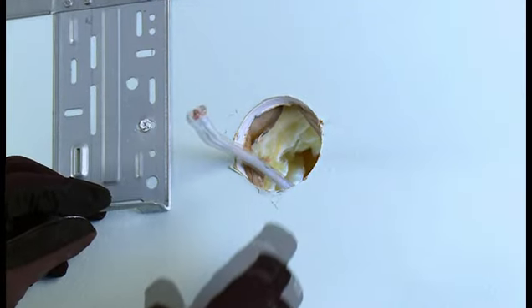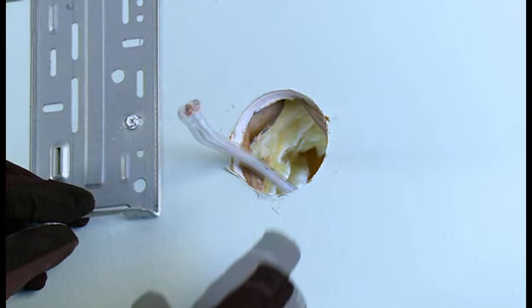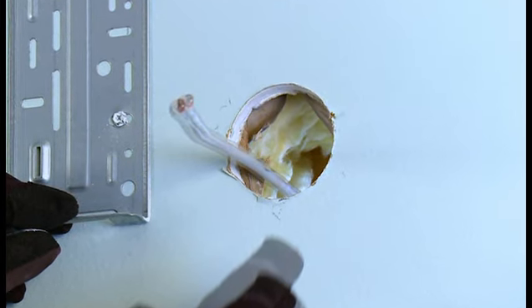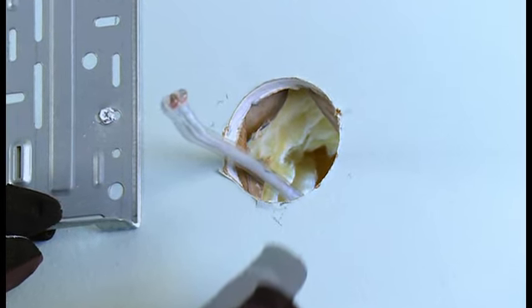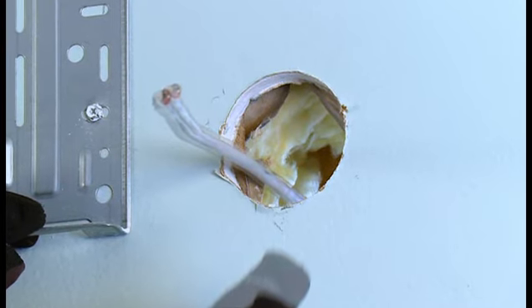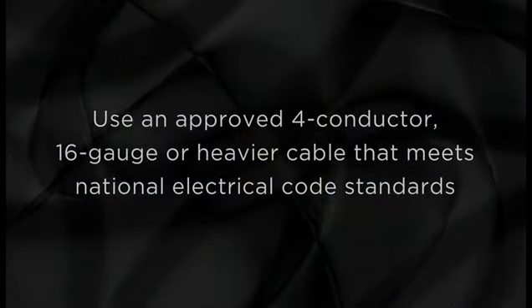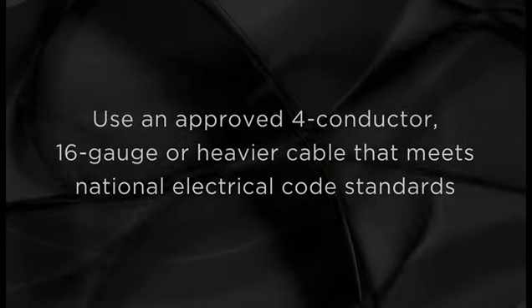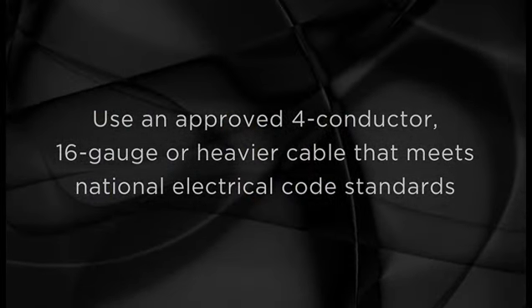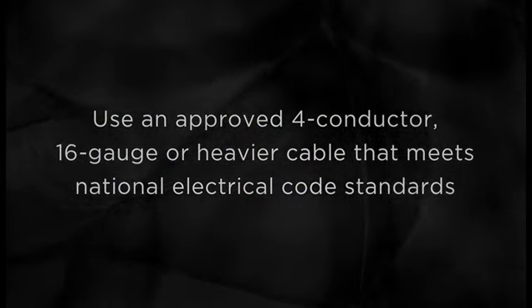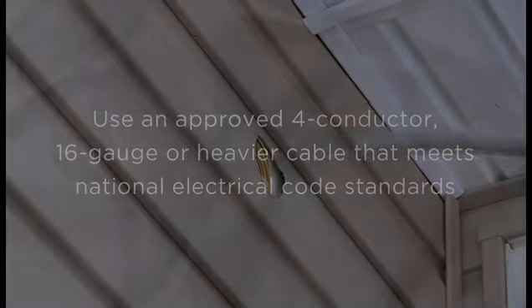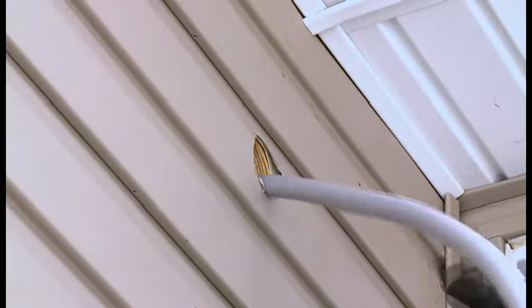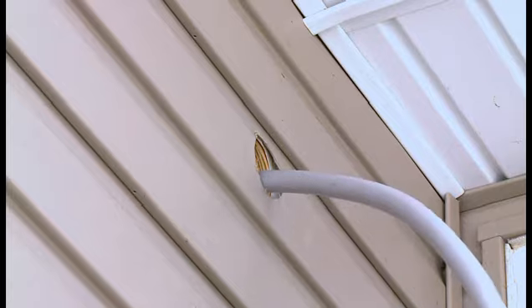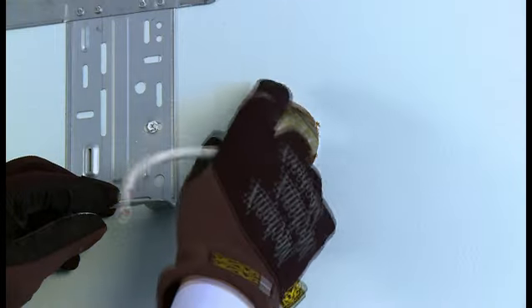To make the interior unit communicate with the exterior unit, a control wire connects the two units. This same wire provides power to the interior unit. In some models, the control wire is included. If your model does not have the control wire, use a 4-conductor, 16-gauge or heavier cable that meets National Electrical Code standards. Thread the control wire through an approved conduit and, then from the structure's exterior, place the conduit and the control wire through the hole in the wall.